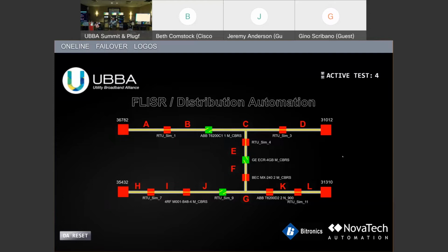Even during those initial operations, it'll send a message saying I've operated so that you have the logs and you know what's going on out there. But if it operates and then closes back in and all's good, you'll just get the operate command, and that'll just kind of be a log and an entry that says, oh, this happened on the system. We might monitor how often it's happening and where.